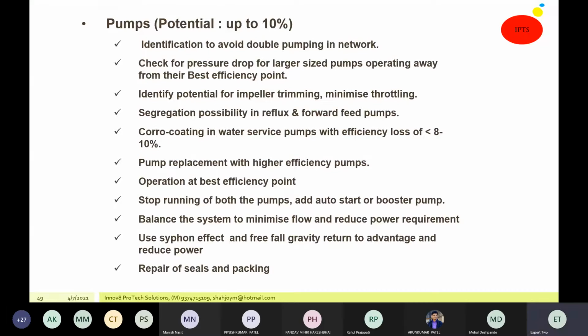Operation at best efficiency point. Stop running of both the pumps. If you go to industry, you will find two pumps running. Why? Because for 10% or 20% additional capacity, one additional pump is operating as a standby pump. So look at whether you can provide a small pump or some booster pump, balance the system to minimize flow and reduce the power requirement.